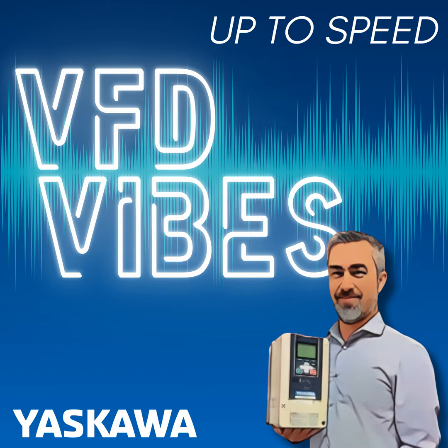You're in front of this drive and it's running, but it's been faulted every morning. You ask the people on site, well, what was the fault? I don't know. It's just the light is solid red and it's sitting there not working. We just turned the power on and off. Now you got to figure out what fault is there. Well, we have additional monitors in the U3 group, which will show you the last 10 faults, and they are date and time stamped, which is pretty handy information to know to see exactly when it's happening.